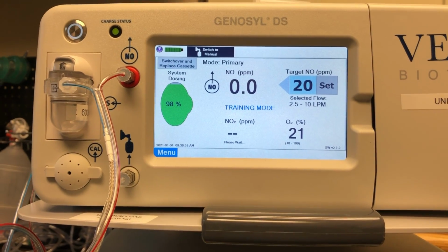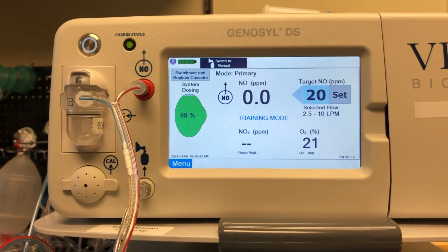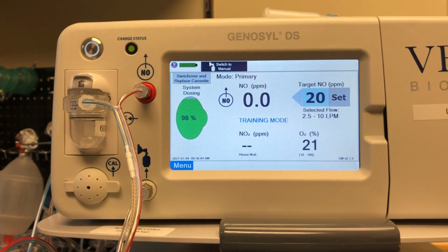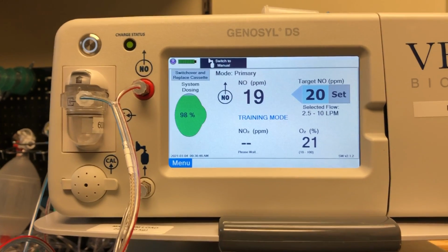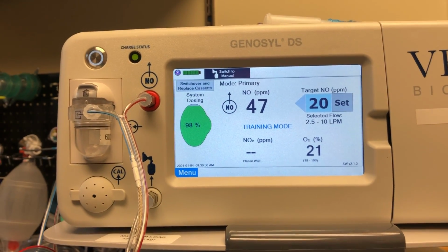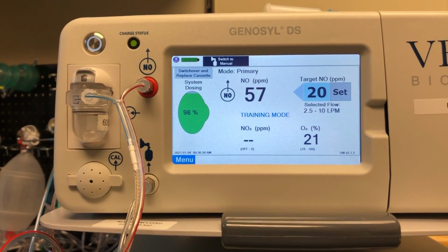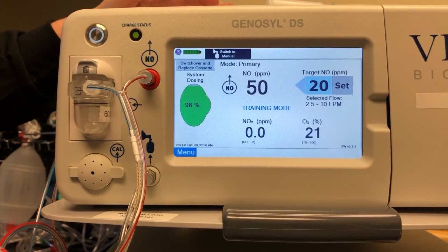Okay, I like it. So we definitely want to flush the circuit as a first step to help remove that excess buildup so that you help prevent the alarm. But most importantly, it's important to recognize for safety purposes that when the alarm happens, nitric oxide delivery stops and you have to resume it. And that's how you do it. You have to get the flow going. You need flow to go.